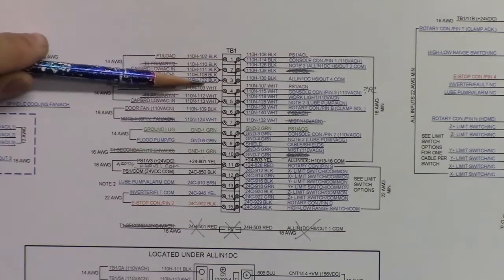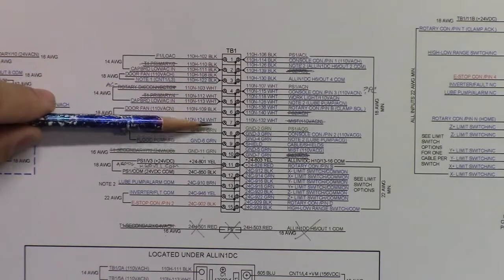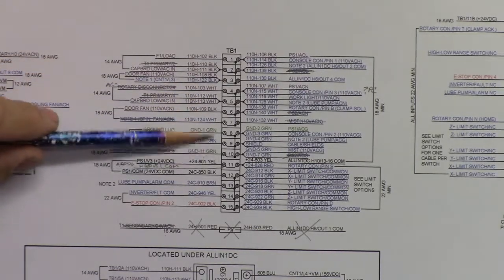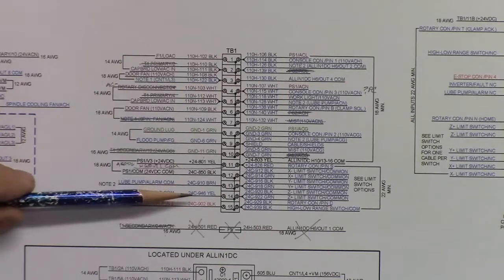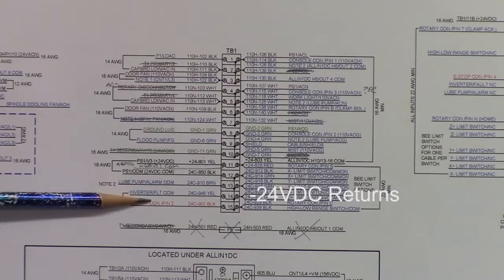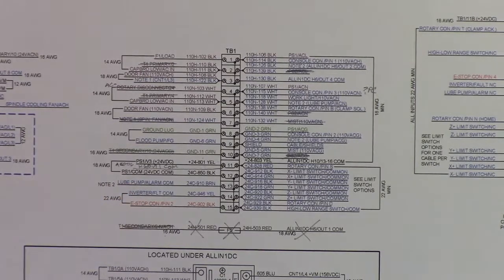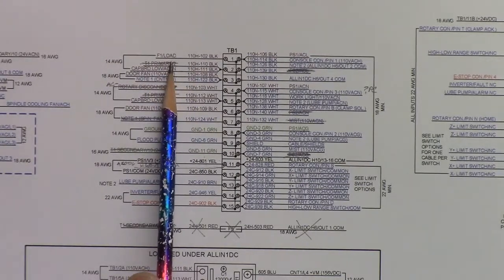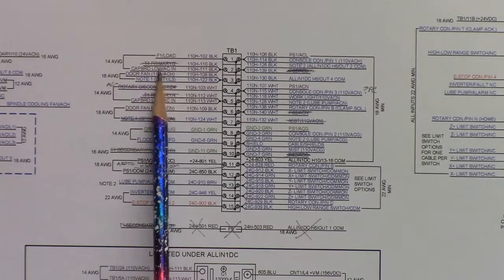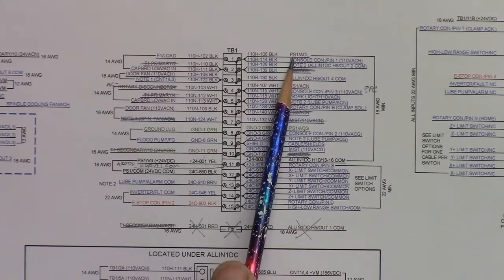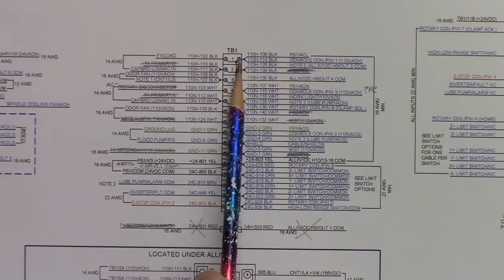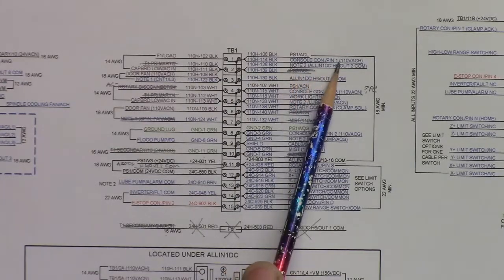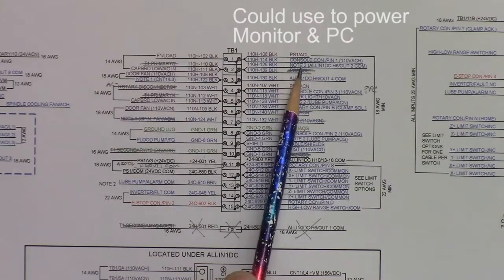It's broken down to 110 volt AC hot, and then 110 volt neutral. And then we get down to the grounds right here. And then we got 24 volts DC here. And then we've got a couple things like pump alarm, lube pump alarm, and inverter fault. So let's kind of go through some of these. F1 load, that's coming from our fuse just past the rotary drum switch. And then it's going to go out, and it's going to feed power supply one. That's the power supply that feeds the all-in-one DC, and also gives us our 24 volt control circuit.